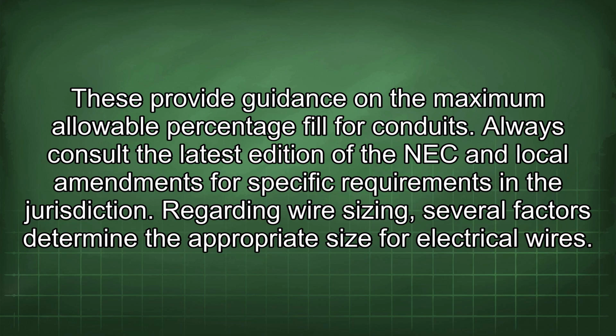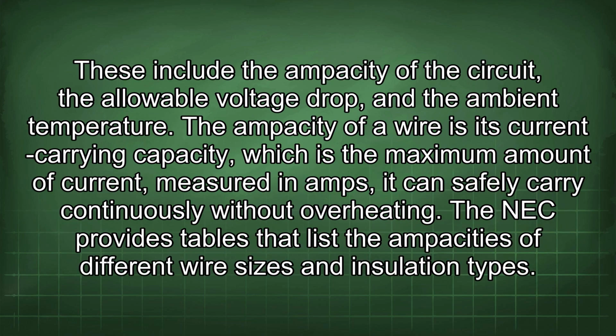Regarding wire sizing, several factors determine the appropriate size for electrical wires. These include the ampacity of the circuit, the allowable voltage drop, and the ambient temperature. The ampacity of a wire is its current carrying capacity, which is the maximum amount of current, measured in amps, it can safely carry continuously without overheating. The NEC provides tables that list the ampacities of different wire sizes and insulation types.